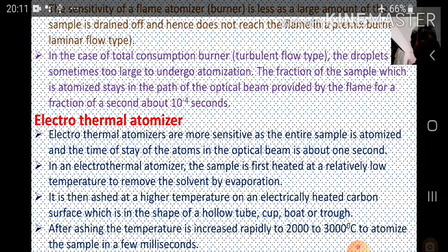The sensitivity of the flame atomizer or burner is less, as a large amount of the sample is drained off and hence does not reach the flame in a premix burner or laminar flow type burner. In case of a total consumption burner or turbulent flow type burner, the droplets are sometimes so big that they cannot undergo atomization. The fraction of the sample which is atomized stays in the path of the optical beam provided by the flame for a fraction of a second, about 10 raised to minus 4 second.